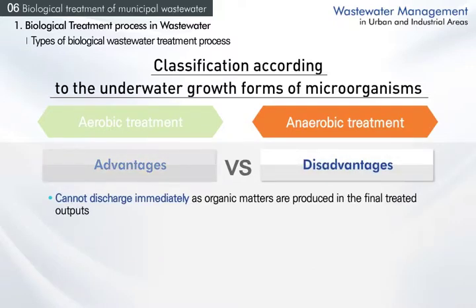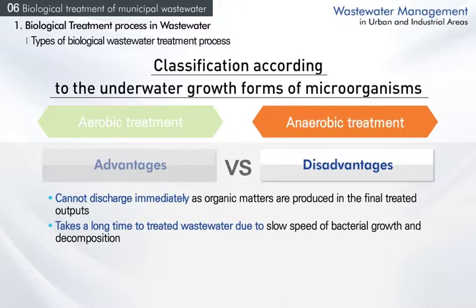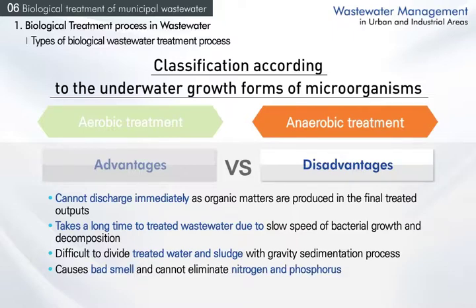Since organic matters other than inorganic matters such as carbon dioxide and water are produced as by-products, treated water cannot be discharged directly to rivers or lakes. Also, anaerobic bacteria grow and decompose pollutants slowly, taking a long time. Maintaining high concentration of microorganisms makes it difficult to separate treated water and sludge with gravity sedimentation. Moreover, anaerobic treatment causes much worse smell than aerobic treatment and cannot biologically eliminate nitrogen and phosphorus. Thus, anaerobic treatment is mainly used for high concentration wastewater or wasted sludge from municipal treatment.